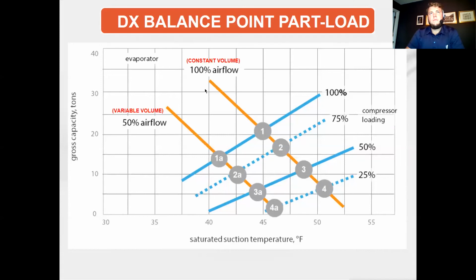So the left-hand curve is showing a variable volume system, and the point 1A here is now fallen because with 50% airflow, the coil will have much less capacity, not necessarily 50% capacity, but less capacity than the design conditions. So this shows how a variable volume system would respond under the same scenario as we turn compressors off.